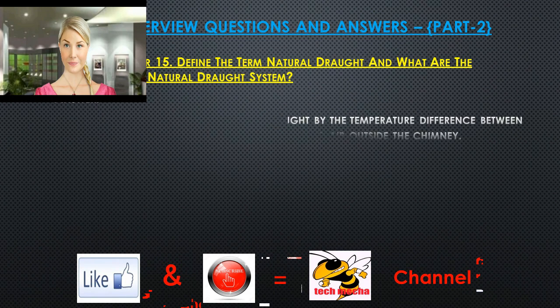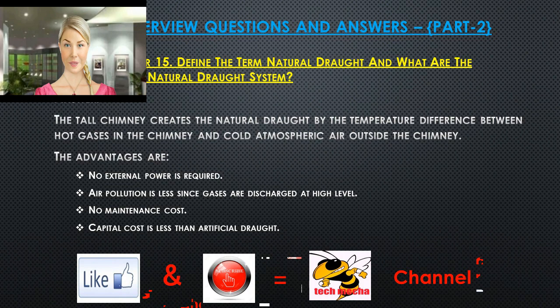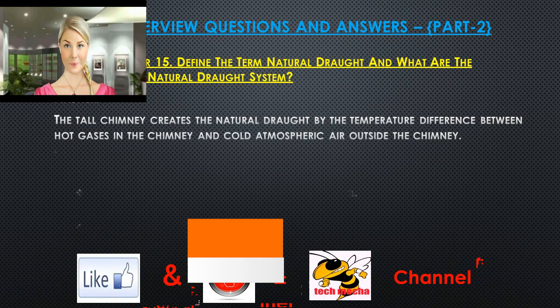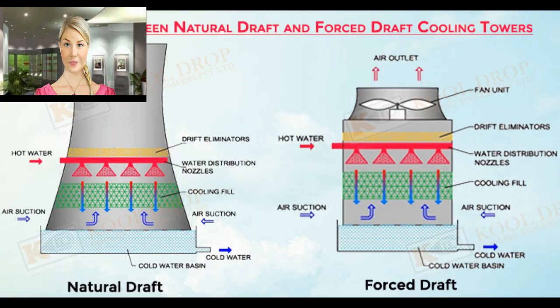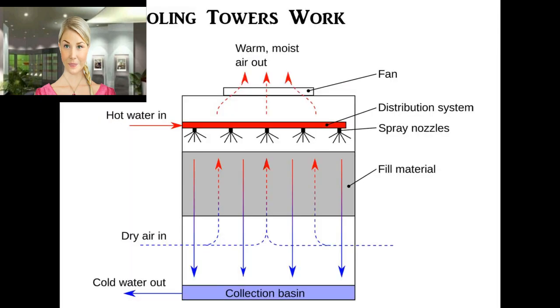Question 15: Define the term natural draft and what are the advantages of the natural draft system? The tall chimney creates natural draft by the temperature difference between hot gases in the chimney and cold atmospheric air outside the chimney. Advantages: no external power is required, air pollution is less since gases are discharged at a high level, no maintenance cost, and capital cost is less than artificial draft.